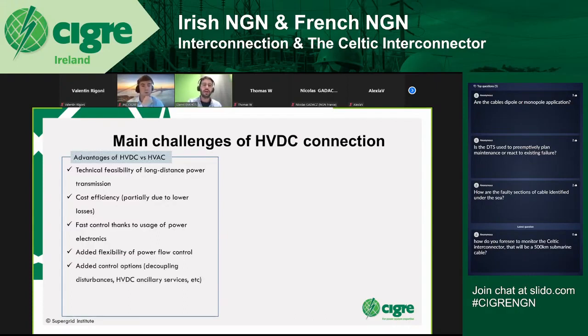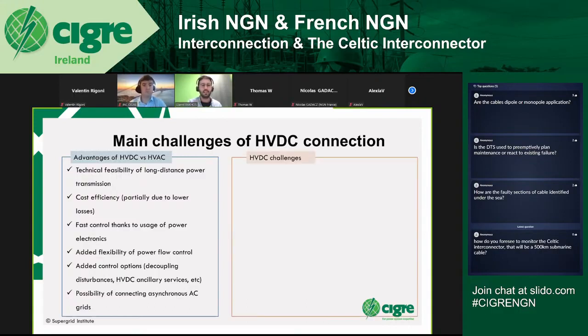to an AC system where power flow is a consequence of the system. We have also added control options to decouple disturbances between AC systems, or disturbance mitigation. Also, HVDC can provide ancillary services to enhance system stability. Finally, HVDC can connect asynchronous AC grids, which is not possible with HVAC links.